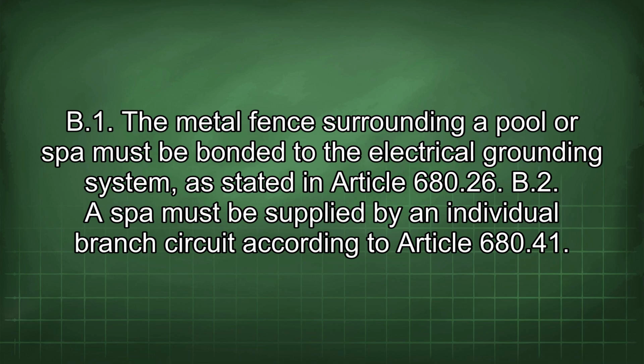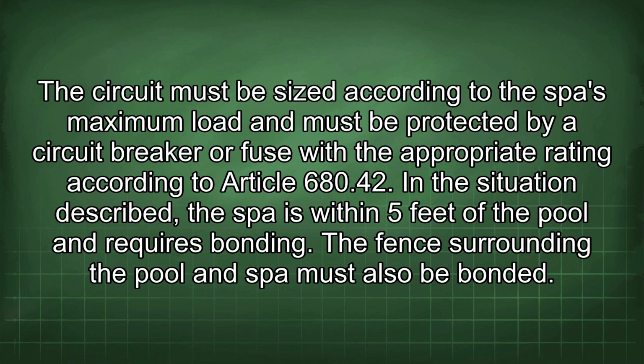680.26.B2. A spa must be supplied by an individual branch circuit according to Article 680.41. The circuit must be sized according to the spa's maximum load and must be protected by a circuit breaker or fuse with the appropriate rating according to Article 680.42. In the situation described, the spa is within 5 feet of the pool and requires bonding. The fence surrounding the pool and spa must also be bonded.